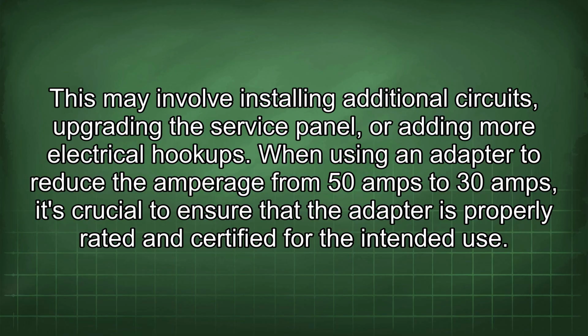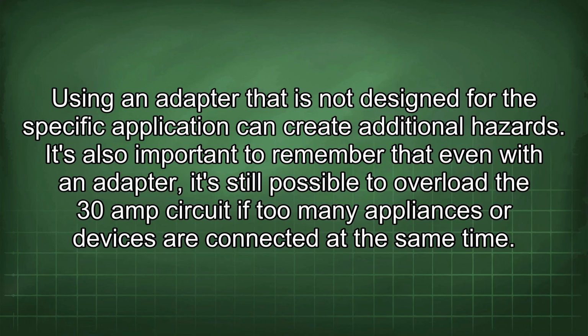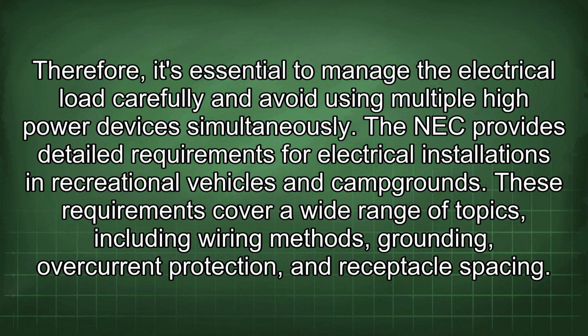When using an adapter to reduce the amperage from 50 amps to 30 amps, it's crucial to ensure that the adapter is properly rated and certified for the intended use. Using an adapter that is not designed for the specific application can create additional hazards. It's also important to remember that even with an adapter, it's still possible to overload the 30-amp circuit if too many appliances or devices are connected at the same time. Therefore, it's essential to manage the electrical load carefully and avoid using multiple high-power devices simultaneously.